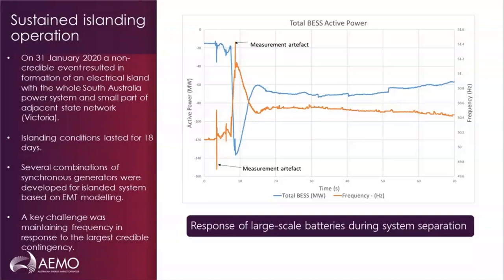For interest of time, I have only focused on one aspect, which is the contribution of battery energy storage systems, and in particular, the fast frequency response that they provide. What we identified is that we needed to increase the combination of synchronous generators that we otherwise have available under system intact condition. When that was achieved, the key challenge identified to operate such a power system was to manage and maintain the frequency within the required frequency band when the system is subject to a credible contingency.